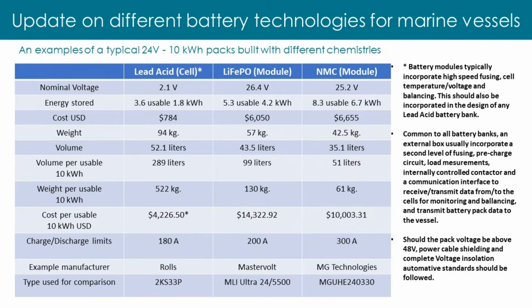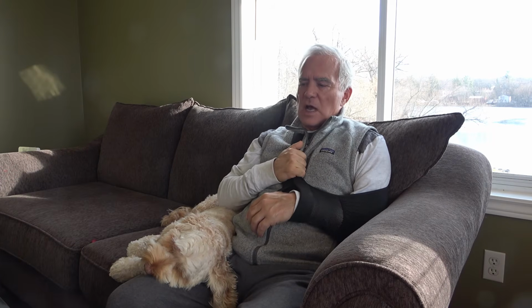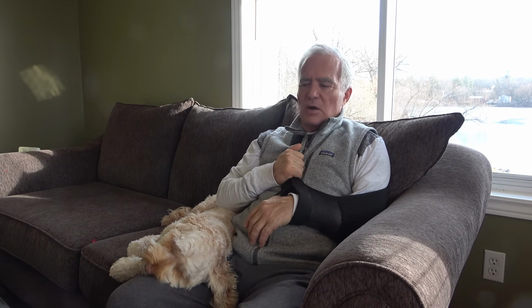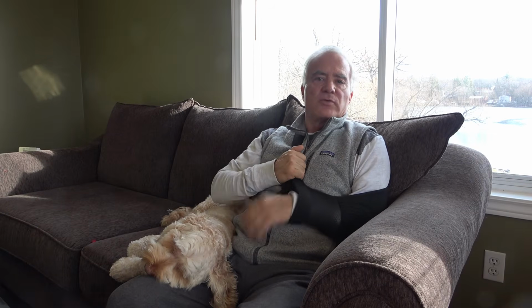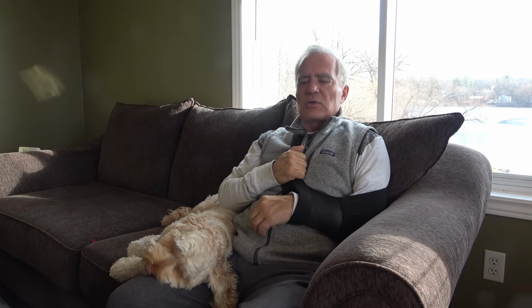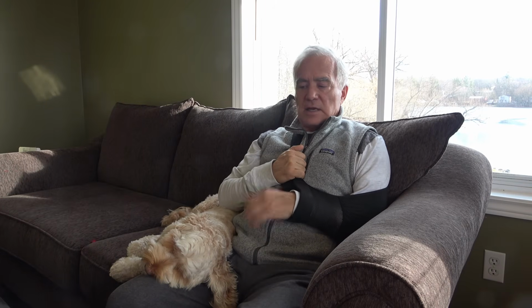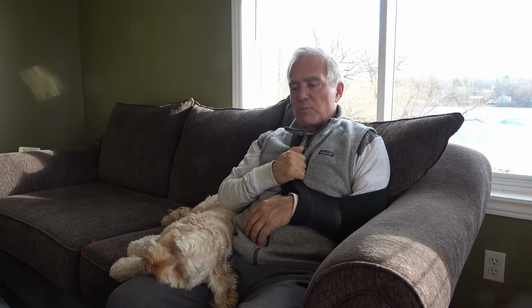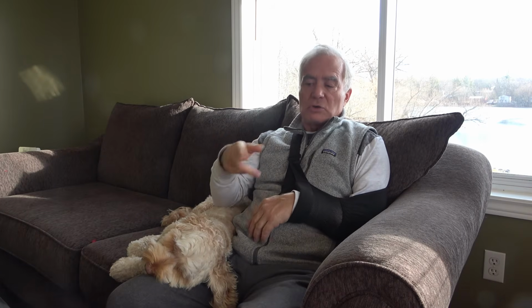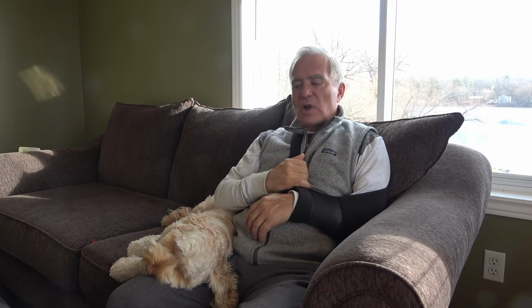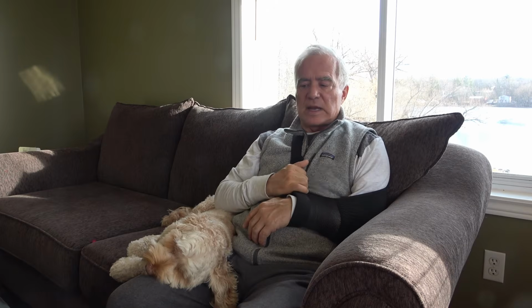Let's walk through the table. People are always wondering about cost, and you have two different cost lines, so tell us about the difference. There's the upfront cost and the amortized cost over the lifetime of the battery. I didn't do these calculations myself, but most of these three types of batteries cycle between 2,000 and 3,000 cycles, which is about 10 years of usage, if not more, so cycle life isn't that much of an issue. Like I said, if a lead acid battery is well built and we run a desulfation cycle every 12 months, and it isn't overcharged or discharged too much, it will last a long time.